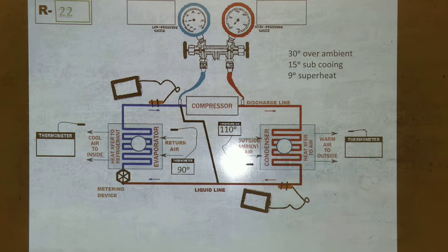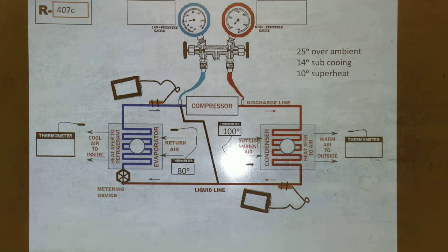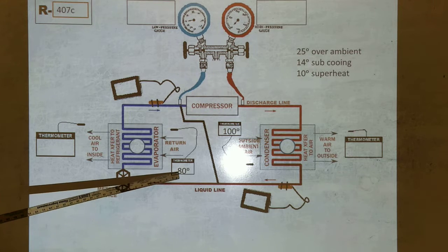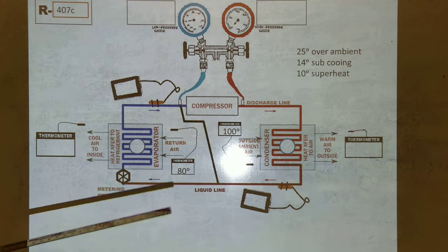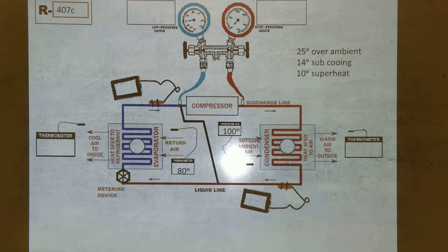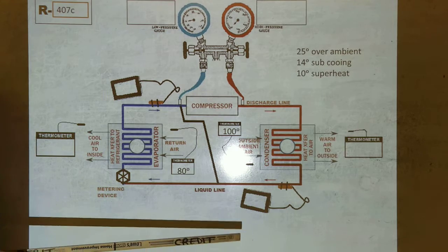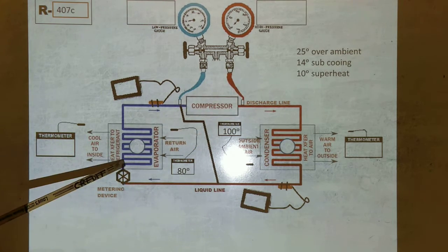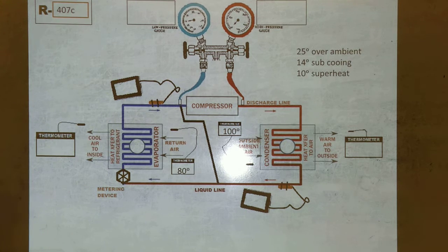Okay, so if we do this, we have a refrigerant of R407C, okay? Same situation, we got 80-degree return air in the house and 100-degree ambient outside temperature. So according to this, we're looking at 25 degrees over ambient temperature for the condensing, and we're looking at, well, we obviously know what that is, right? Our approach and our temperature difference.